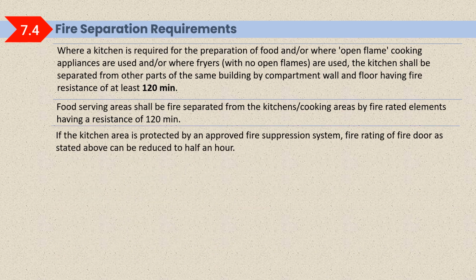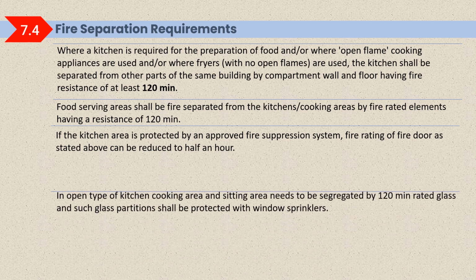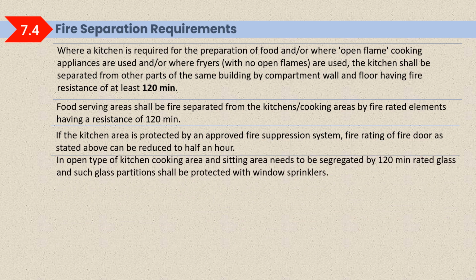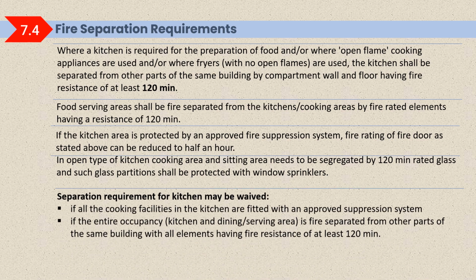If the kitchen area is protected by an approved fire suppression system, the fire rating of the fire door as stated above can be reduced to half an hour. In an open type of kitchen, the cooking area and sitting area need to be segregated by 120-minute rated glass, and such a glass partition shall be protected with window sprinklers.